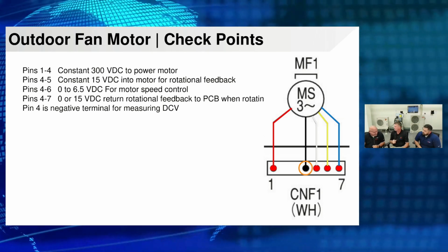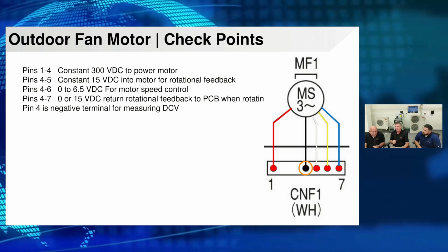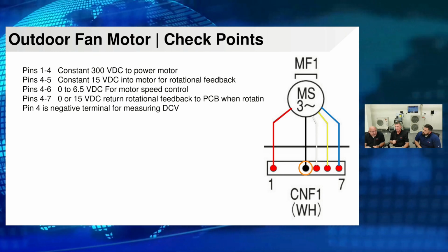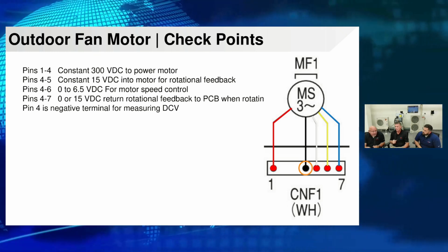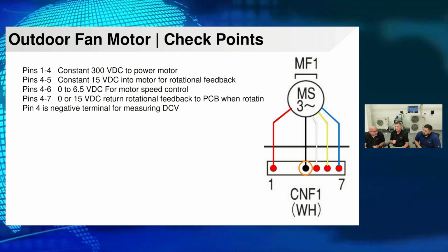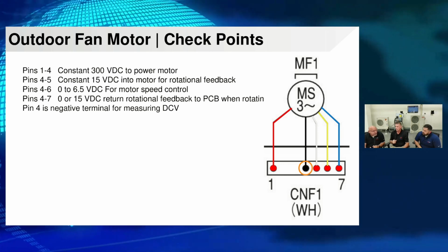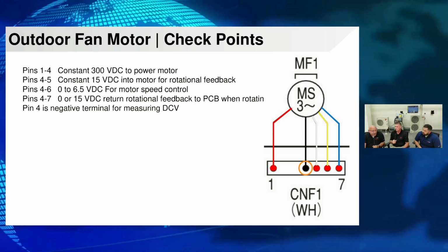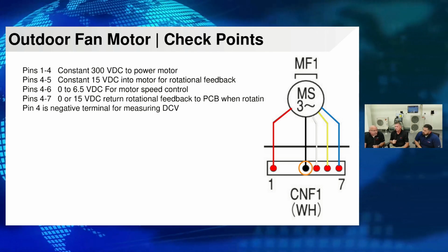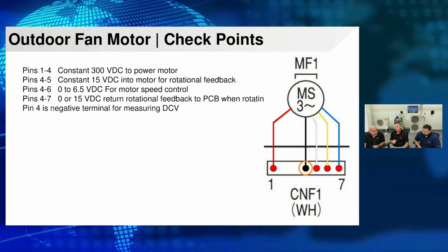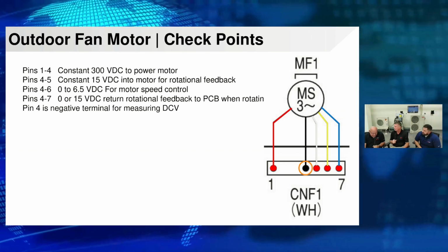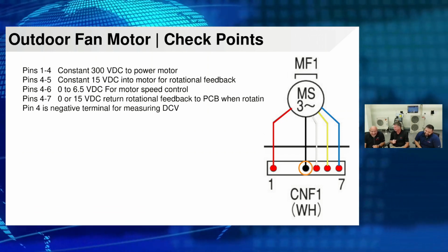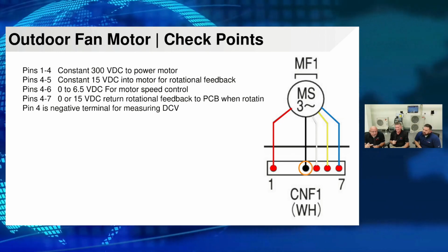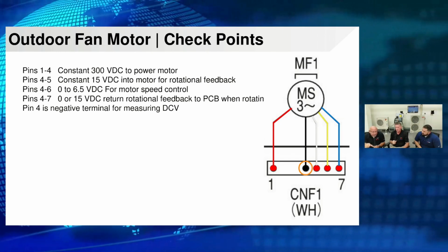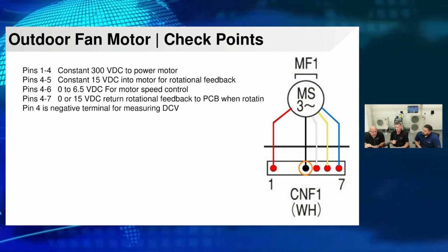We'll use that signal again. Pins 4 and 6 is your speed command, and that signal is 0 to 6.5 volts. So if it's 0, that motor should not be running. If it's 6, that motor should be turning almost to high speed. Looks like a variable speed ECM to me. And then 4 to 7 is that 15 volts DC signal coming out of 4 and 5.